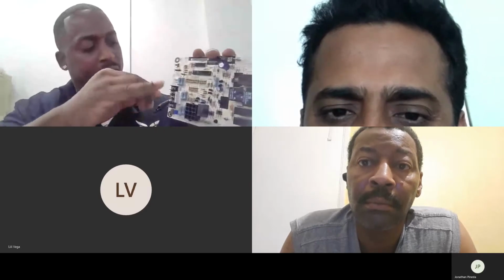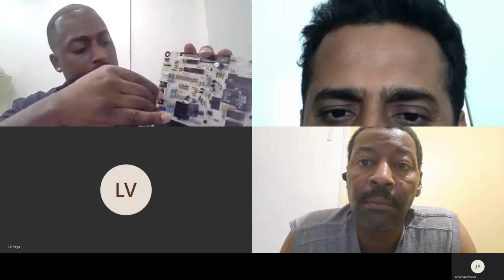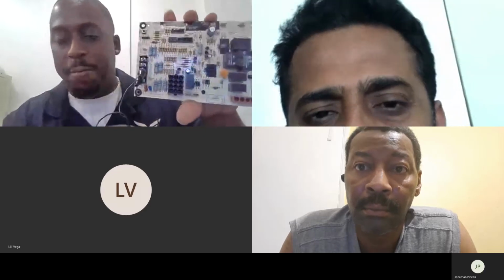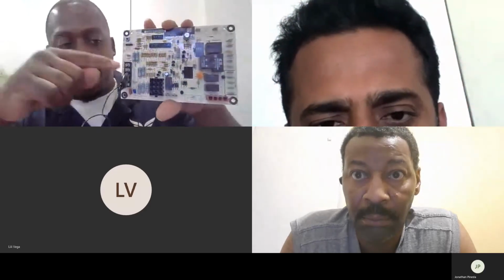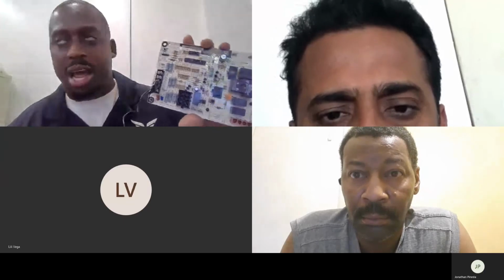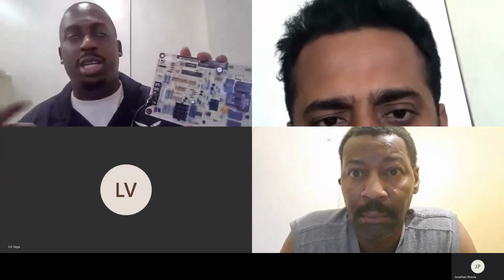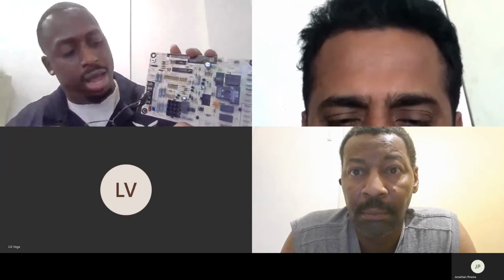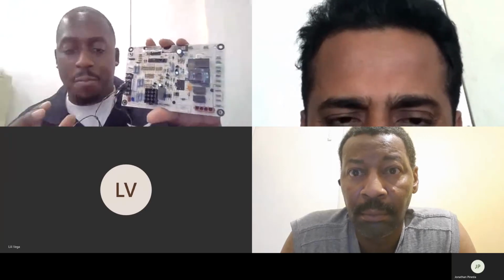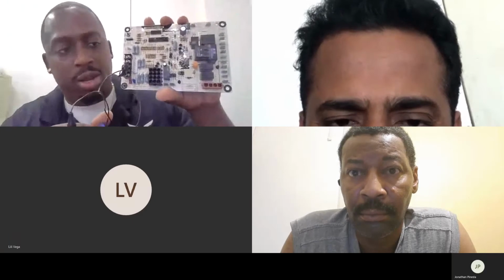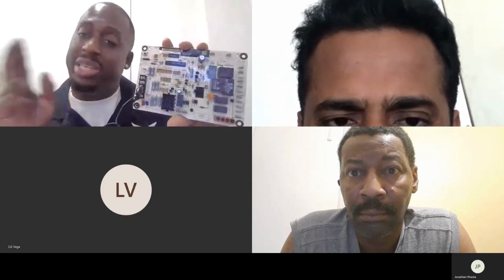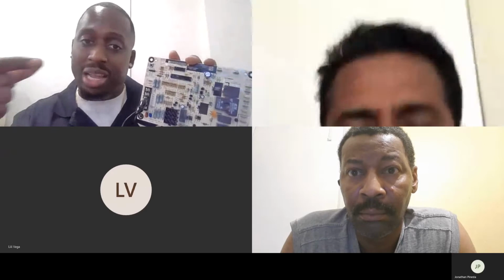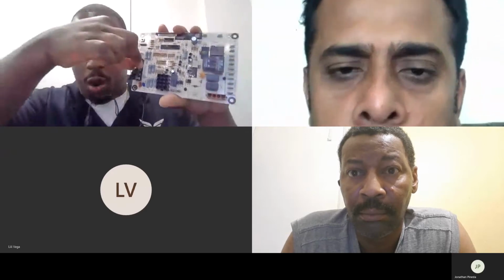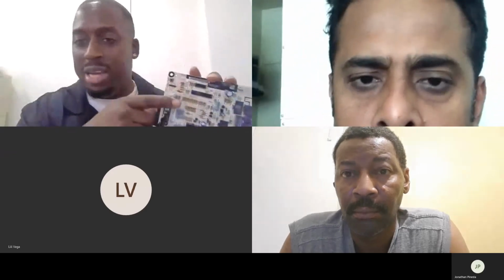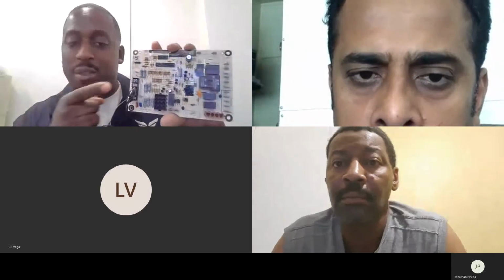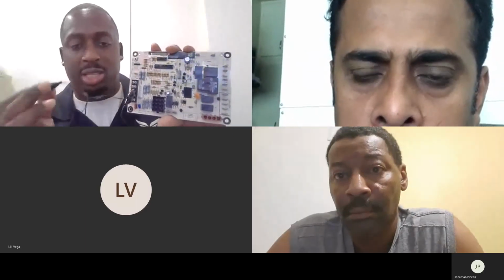If I want to test my fan, boom, as soon as I do that, the fan will start turning, because I just forced power from R to G. And now, okay, I see the fan works. Now let's say I want to test the cooling. I'll go ahead and grab another one. And this is why I like to wire up multiple jumpers together, because if I wanted to do a second thing, I would have to connect a second clamp to R, and then the other end of that one to whatever the next thing is. But the way I'm doing it, I only have to put one thing on R, and then I can just jump right to the next thing.